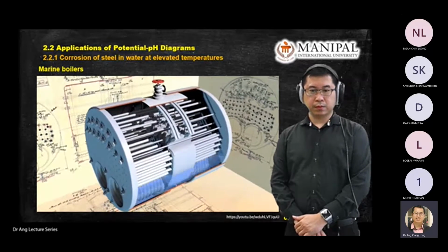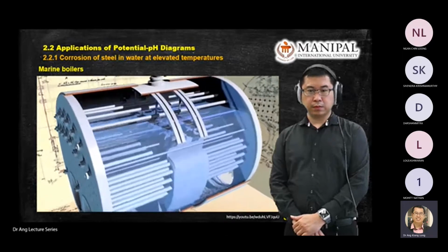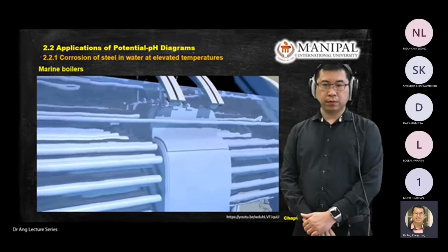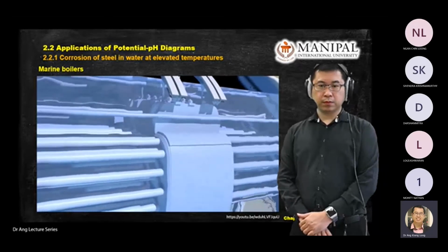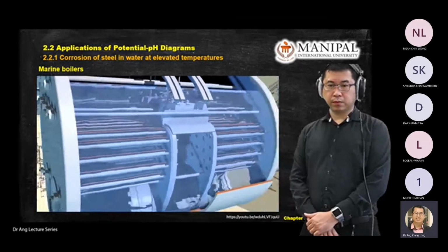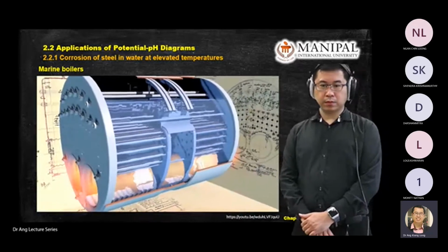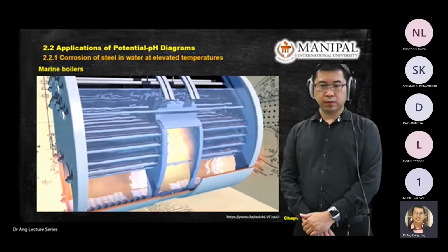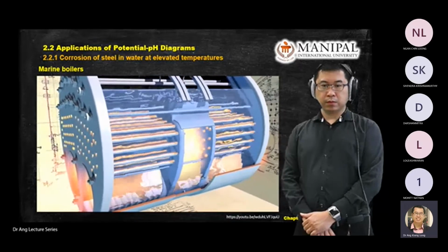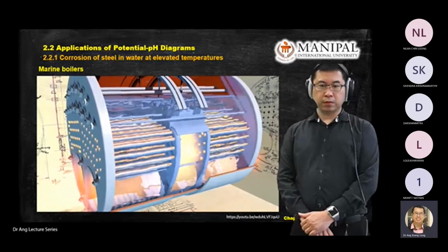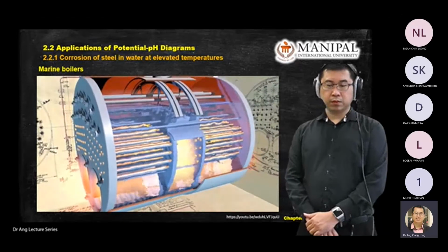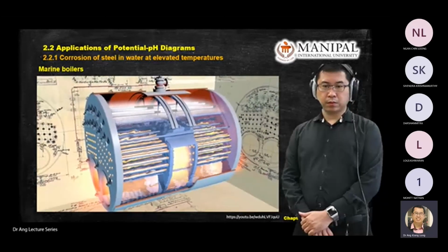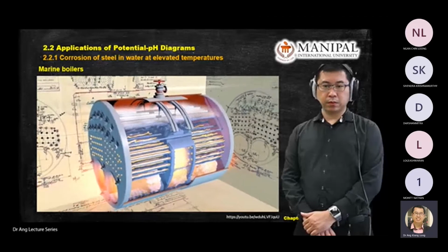The boiler is now filled with water. Note that the crown of the combustion space and all the tubes must be covered by water to prevent overheating and potentially catastrophic failure. The furnaces are then lit from both ends of the boiler. Hot gases pass through the furnaces into the centre, up through the fire tubes and then out to the exhaust. These fire tubes heat the water that creates the steam, which is collected at the top of the boiler and then distributed via the valve.